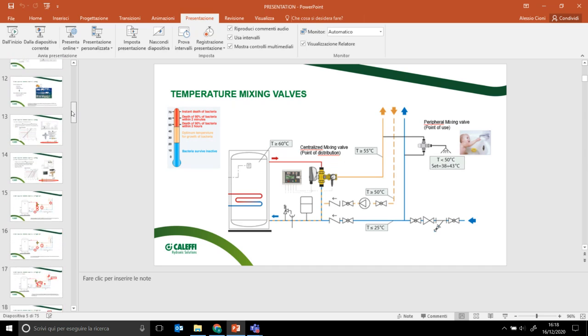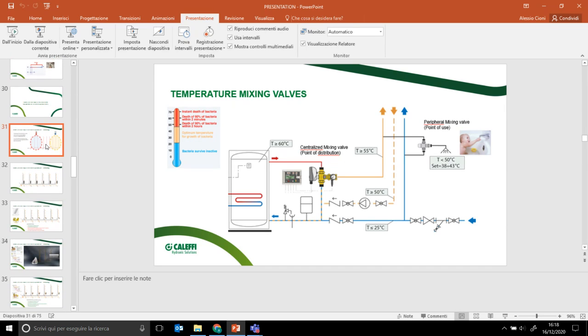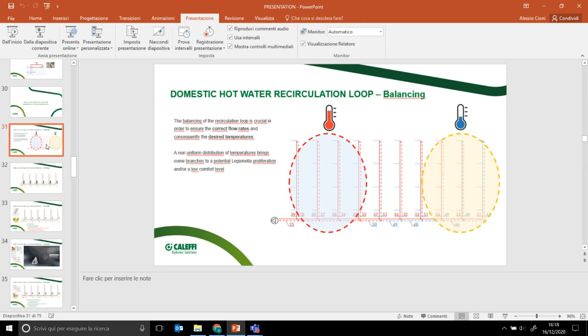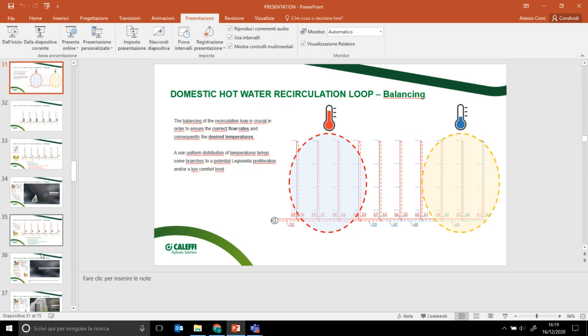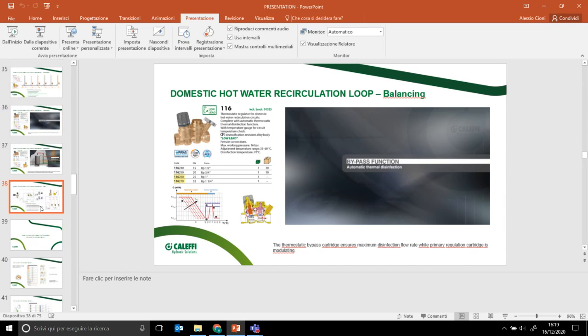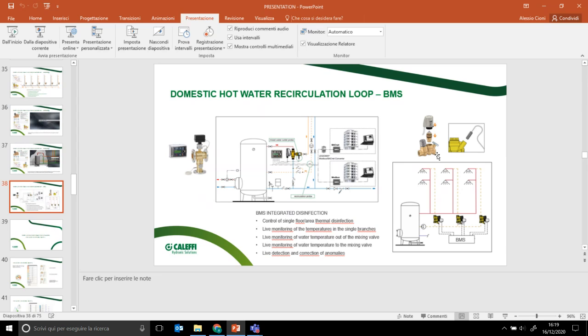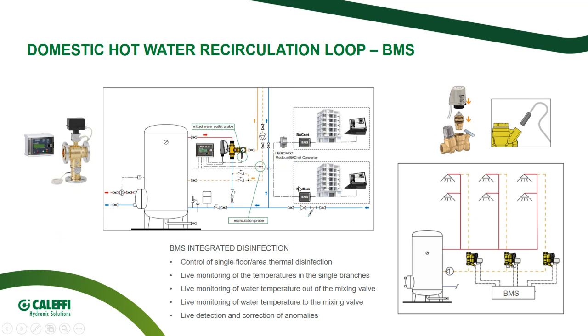So previously, we mentioned that even if everything is sized correctly, the mixing valve is operating correctly, and the water has the right temperature, but it is distributed in a non-correct way, all my efforts will not be successful. So also a correct system balancing has to be verified. So that's why our recommendation is to equip the thermostatic balancing valve with a temperature sensor. This is the most complete configuration in order to ensure that all the branches have the right temperature.